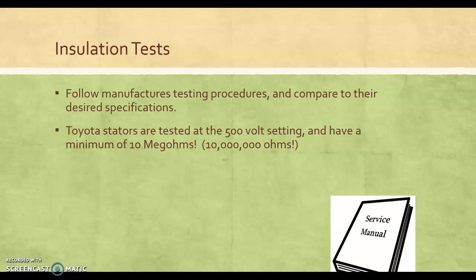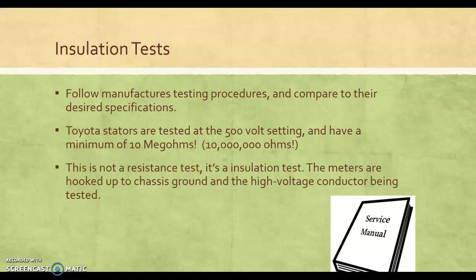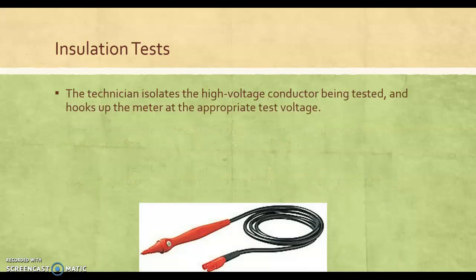So if you have a direct short, the Bosch FSA 050 will display 10K when it could be a direct short. Pay attention to your units. And also tech tip, if you see less than 100 mega ohms, start thinking you have a breakdown imminent. Something's happening. So, yep, be aware.